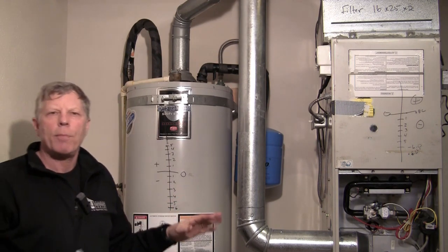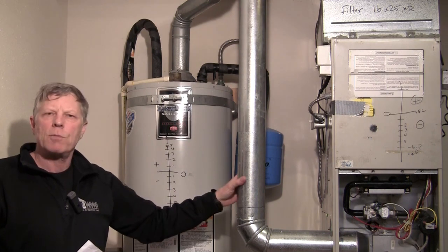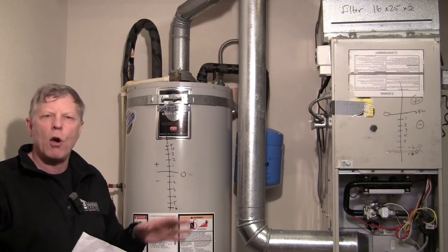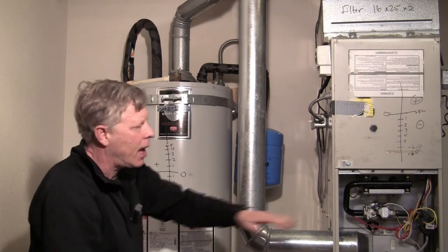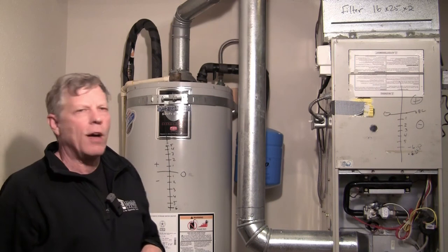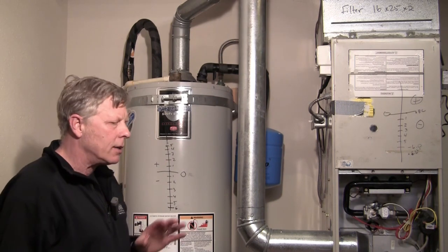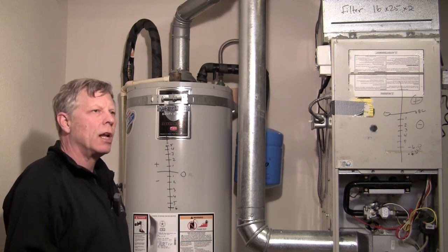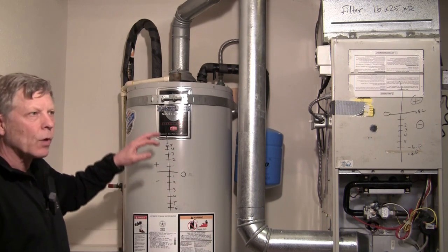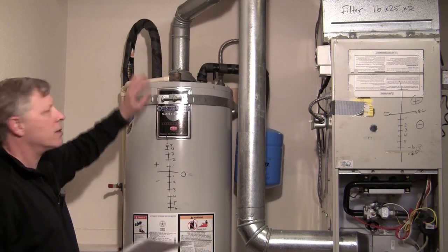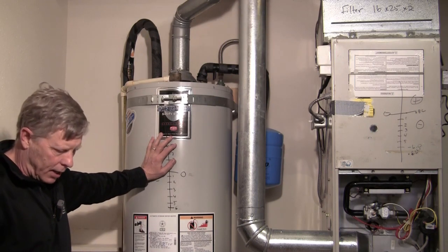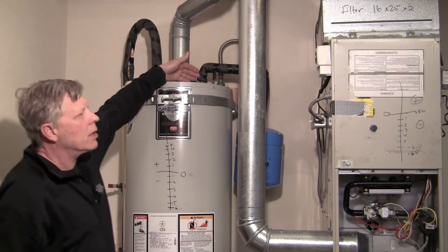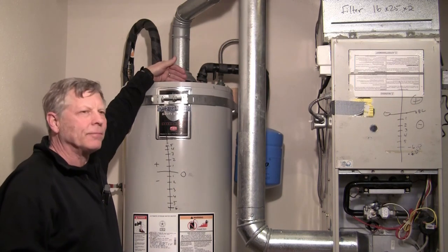I've also set up thermometers on my furnace because I'm going to move right on to testing my furnace. So I've got thermometers on my furnace ready to go for heat rise. I've checked the label on my furnace. It's 35 to 65 is what we're looking for on the heat rise. I have my combustion analyzer ready to go so that once I hit the 5-minute mark I can test the CO and the appliance. So we're in about a minute. I can still smell it.